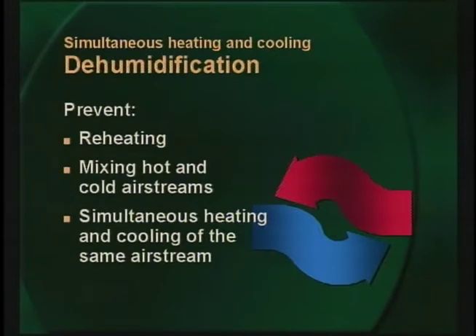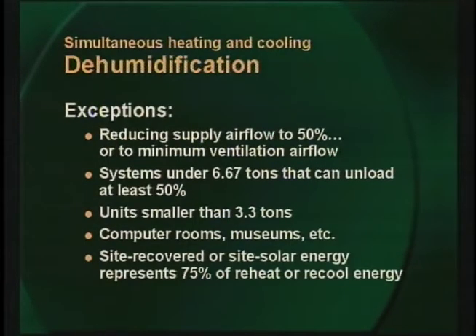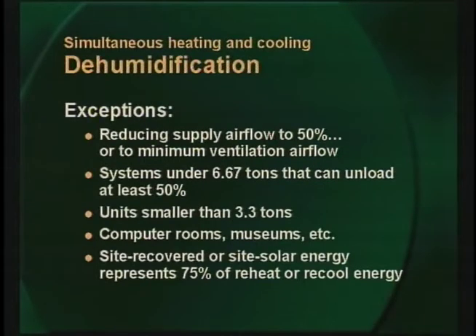There are exceptions to this limitation. The system capacity must be reduced prior to reheating, or it must be a small unit. Process applications include computer rooms, museums, surgical suites, supermarkets, and ice arenas. Again, if the energy to reheat or recool is recovered, you may do as much reheat as necessary. In my opinion, the reduction of new energy reheat will lead designers to recover heat from the cooling process. This heat may be recovered in a number of ways: from a chiller using either a condenser bundle or an auxiliary heat recovery condenser, from a refrigerant system desuperheater or a heat recovery coil, or from other energy recovery options such as an air-to-air heat exchanger.